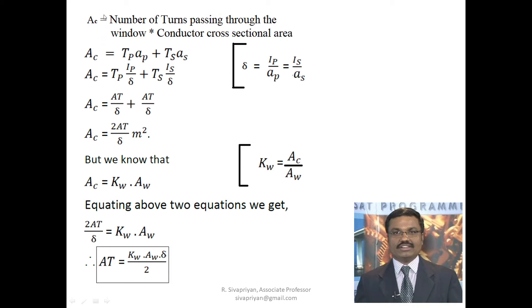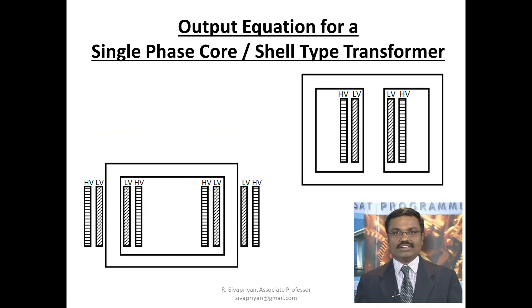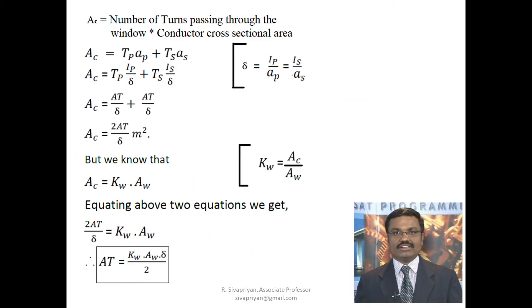For single-phase core type transformer, all the LV windings and all the HV windings pass through the single window, so all primary and secondary turns pass through that one window. For the shell type transformer, there are two windows — taking either window, all primary windings as well as all secondary windings pass through it. So the Ac calculation method is the same for both types.